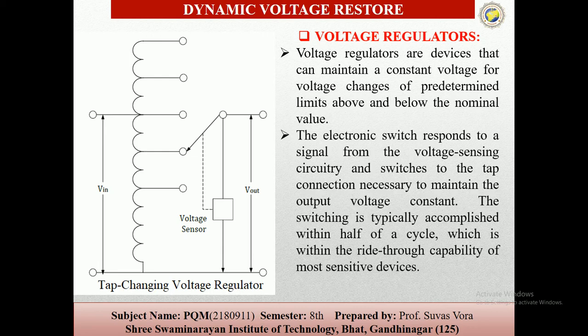So the electronic switch responds to the signal from the voltage sensing circuitry and switches the tap connections as necessary to maintain the output voltage constant. The switching is typically accomplished within half of a cycle, which is within the ride-through capability of the most sensitive devices. So these are other techniques for voltage regulators, commonly used as a filter or notch filter, which produces low impedance, achieved by employing capacitor banks. Generally, we can achieve this with a capacitor bank.